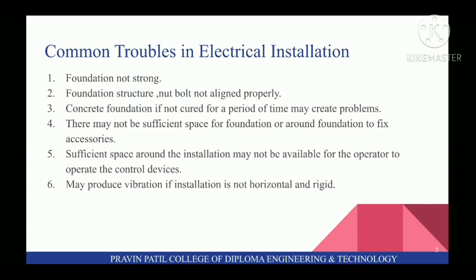First is Common Troubles in Electrical Installation. The first trouble is Foundation Not Strong. Second is Foundation Structure Nut Bolt Not Aligned Properly. Third is Concrete Foundation, if not cured for a period of time, may create problems. Next, there may not be sufficient space for foundation or around foundation to fix accessories. Fifth, sufficient space around the installation may not be available for the operator to operate the control devices. Sixth, may produce vibration if installation is not horizontal and rigid.